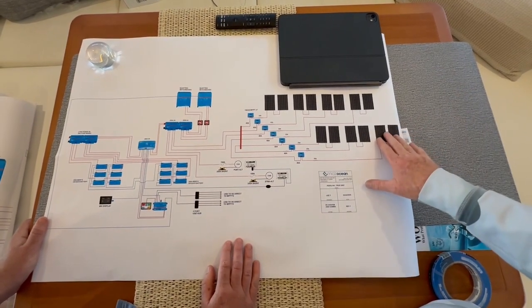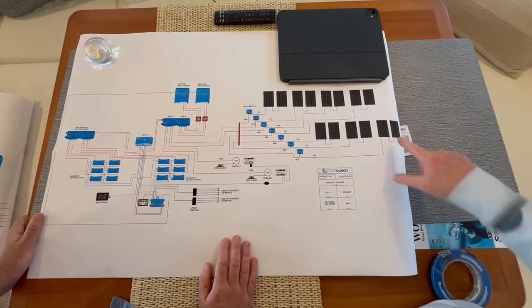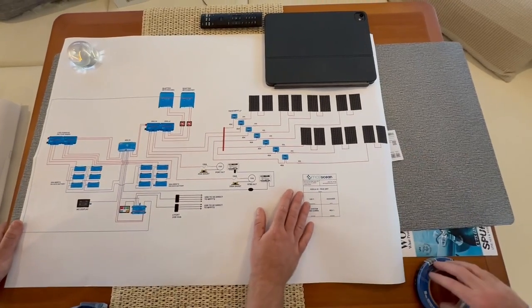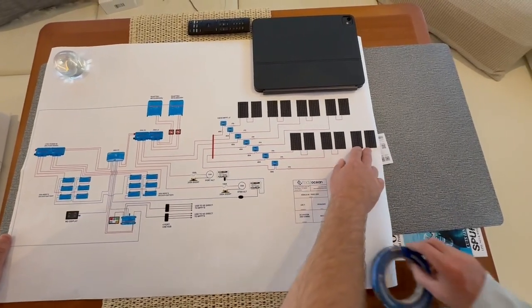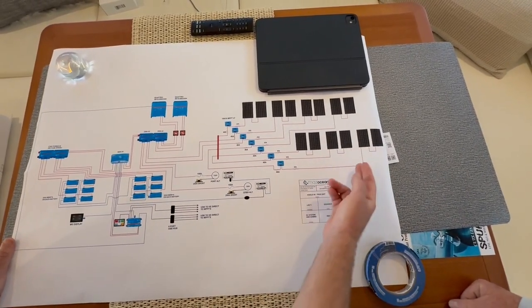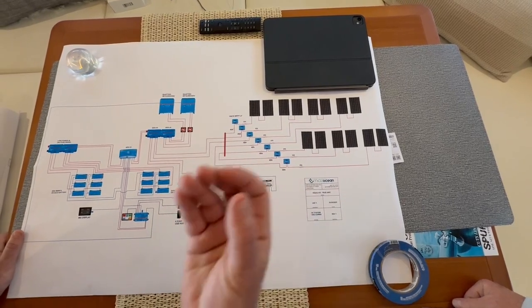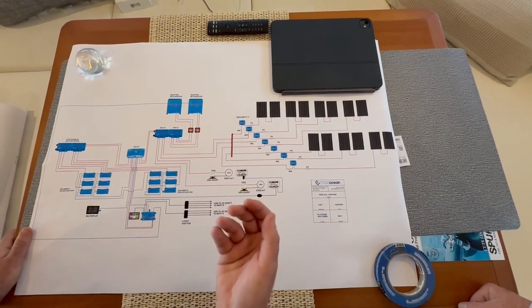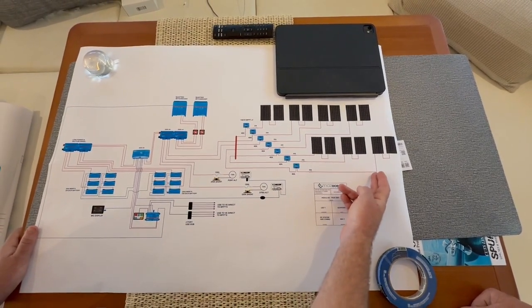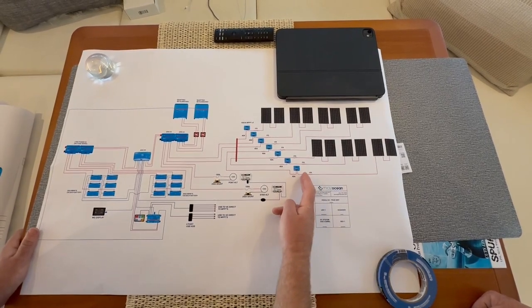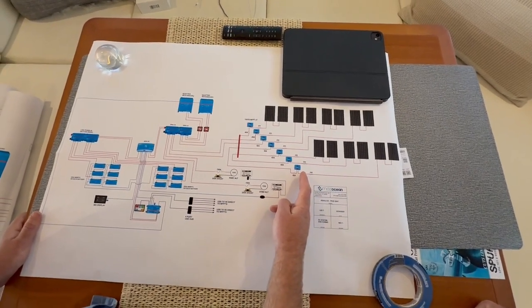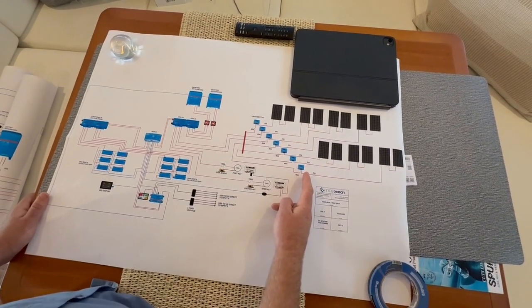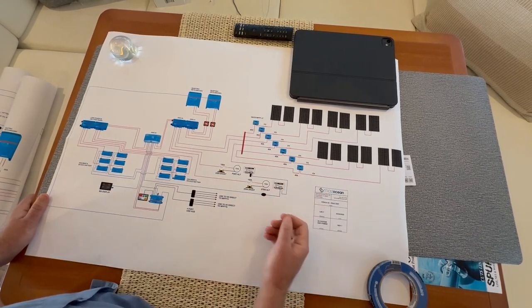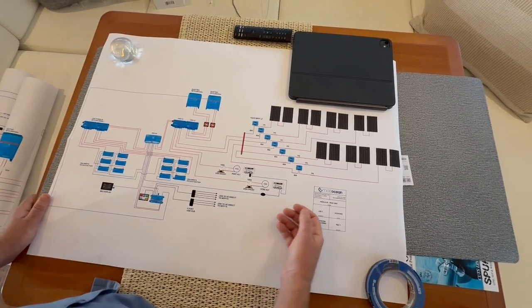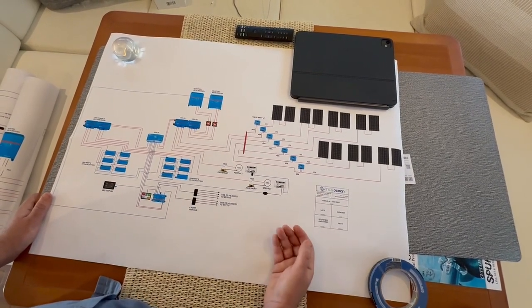So from the panels, why are they tied together in twos? Basically, we've wired the panels into series pairs. By seriesing panels, we're increasing the voltage, and by increasing the voltage we're reducing the wire size required, which makes it a little easier. If we'd wired all of these in parallel instead, the wire sizing would have needed to be bigger. Also, the higher the voltage, the more efficient things are.